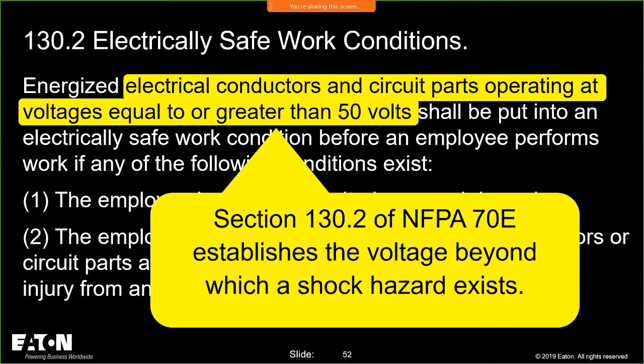Now, if we look at 130.2, remember 130.4, we had the exception, but this was the section I was looking for earlier. For some reason, my sticky note fell off. 130.2 is where it says energized electrical conductors and circuit parts operating at voltage equal to or greater than 50 volts. That's your line in the sand. So 50 volts. Now, I know they've done a lot more. They're trying to understand DC a lot more. I've heard 100 volts on DC, but there's no AC or DC associated with 130.2. It's 50 volts.